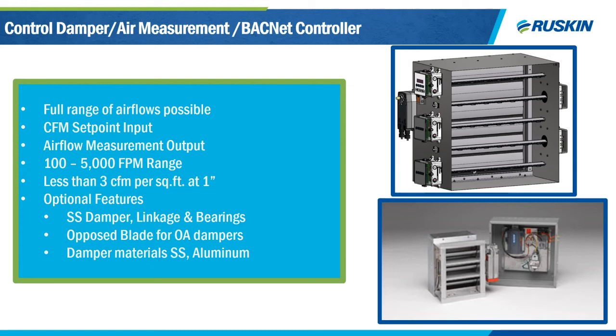The combination of a damper with an air measurement station and controller in one unit is something Ruskin does best as our Airflow IQ. Any Ruskin control damper can be combined with our advanced thermal dispersion air measurement probes in a 15-inch sleeve with a modulating actuator, providing air measurement with controls from Ruskin. Electronic air measurement can control airflow as low as 100 feet per minute, and velocity pressure can control airflows as low as 300 feet per minute — either can work up to velocities as high as 5,000 feet per minute. When paired with our CD50 damper, this is a low-leak Class 1A damper with less than 3 CFM per square foot leakage at 1 inch of water column. We recommend an opposed blade damper for outside air applications to get the best control at the lowest flows.